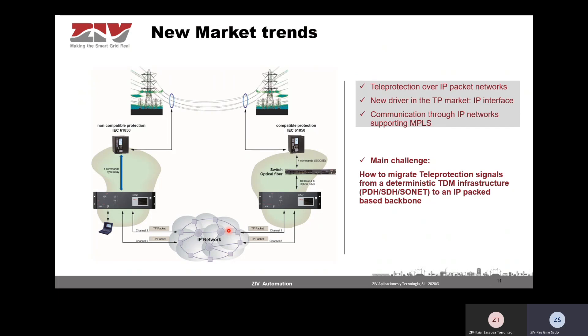Now I'm going to talk about a new market trend: teleprotection over IP packet networks. In this case, the line interface is an IP packet interface — what we call a new driver in the teleprotection market. Many utilities are using IP networks or IP networks supporting MPLS. The technology of communications networks is evolving towards packet switching solutions, and while telecom service providers have been leading this change, power utilities are now following this trend.